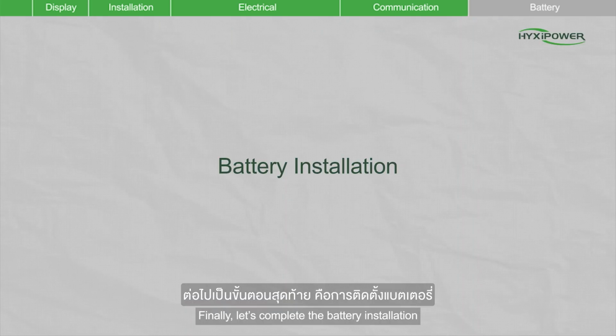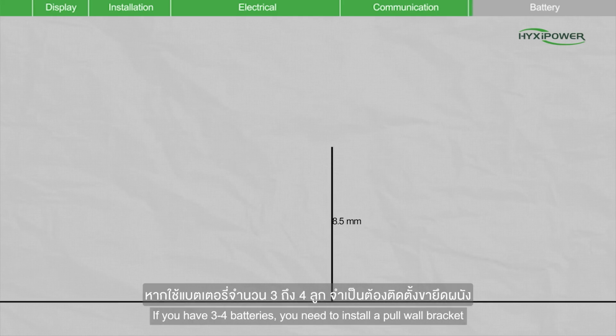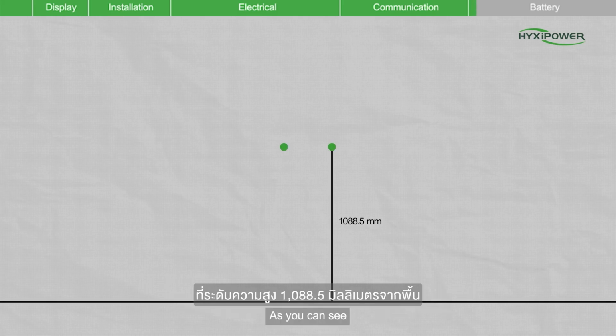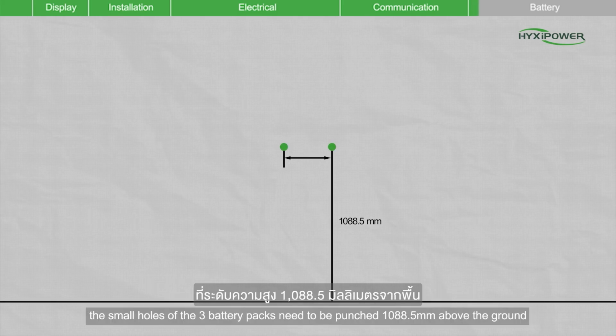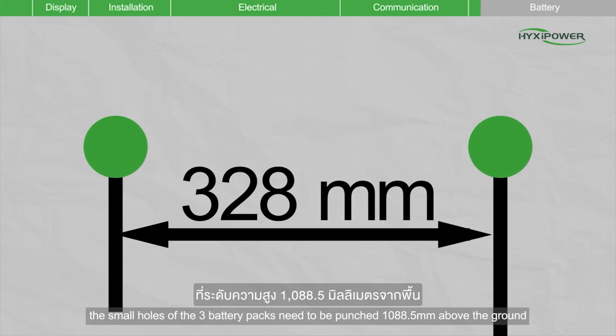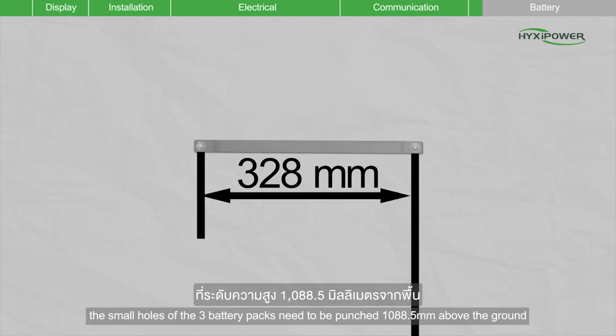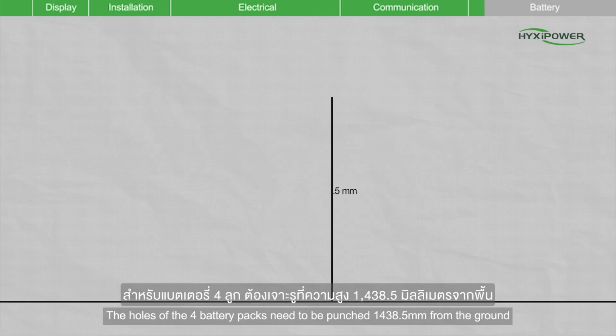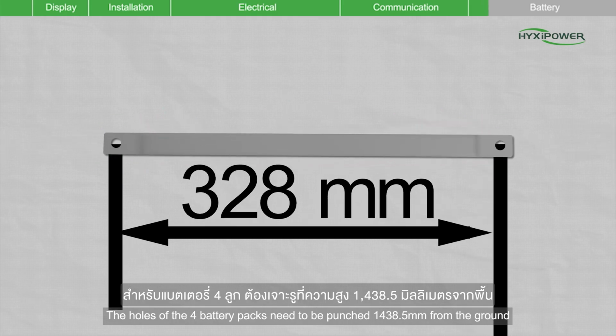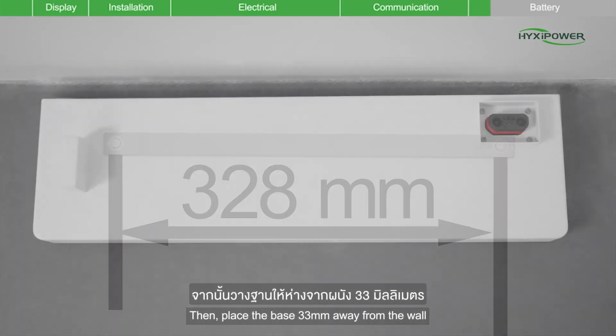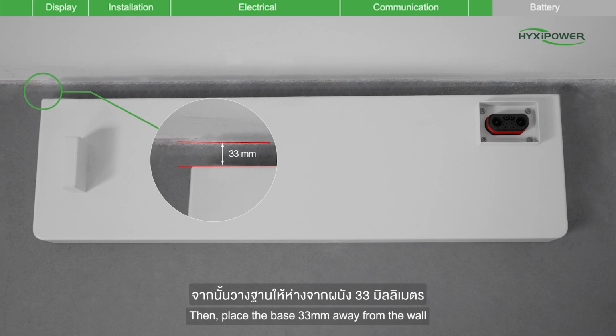Finally, let's complete the battery installation. If you have 3 to 4 batteries, you need to install a wall-mounted bracket. As you can see, the holes for 3 battery packs need to be drilled 1088.5 mm above the ground. The holes for 4 battery packs need to be drilled 1438.5 mm from the ground. Then, place the base 33 mm away from the wall.